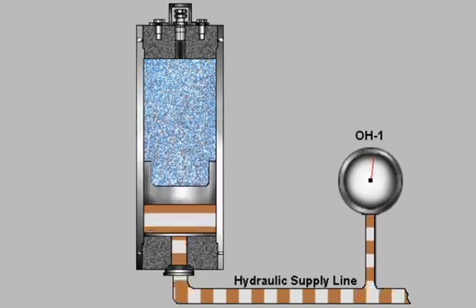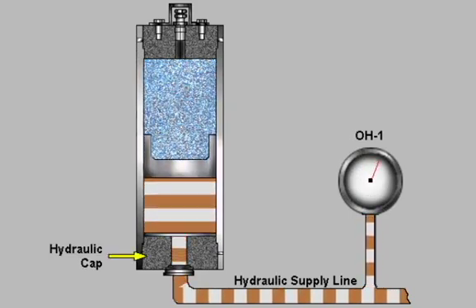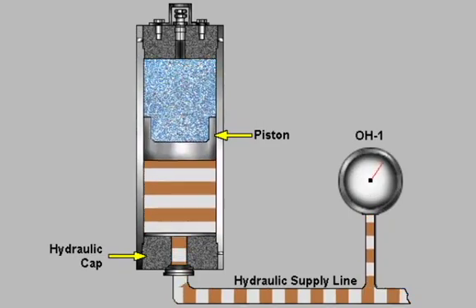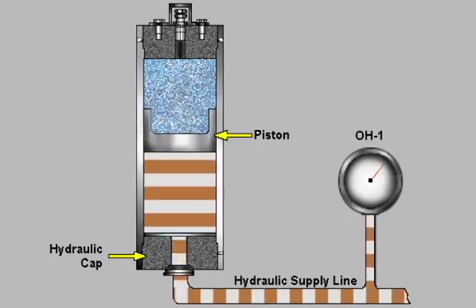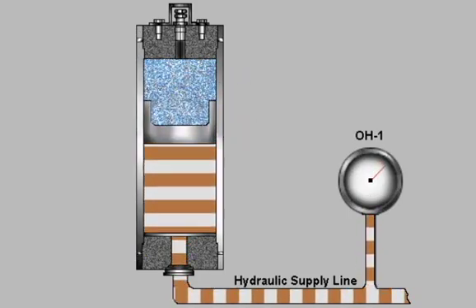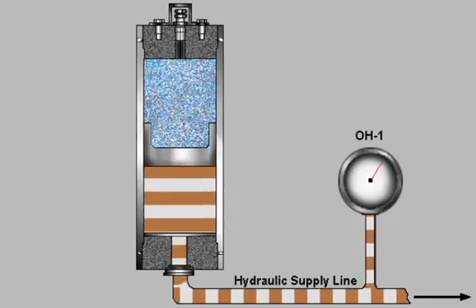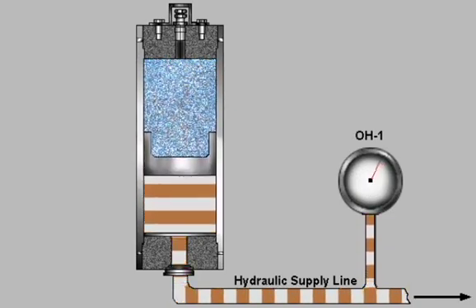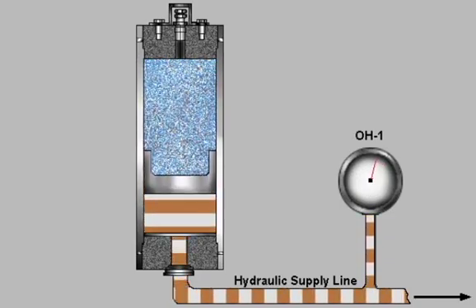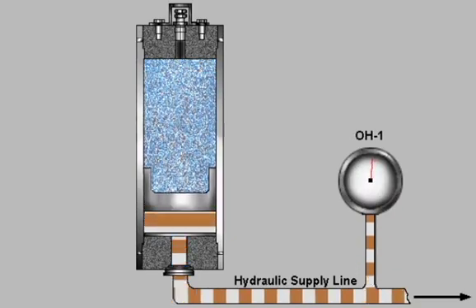Hydraulic oil enters each accumulator through the hydraulic cap and acts on a piston to compress an inert gas, usually nitrogen. If hydraulic oil pressure decreases at the accumulator inlet, the gas expands and forces hydraulic oil back out into the hydraulic supply line.